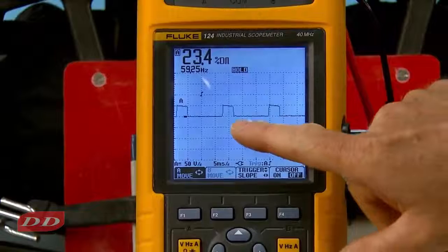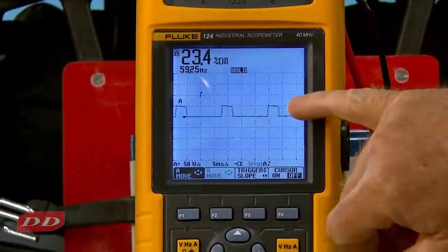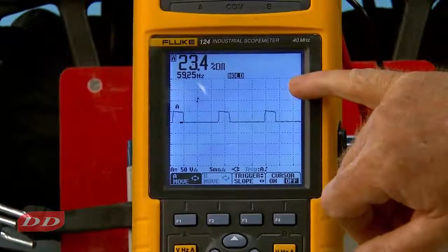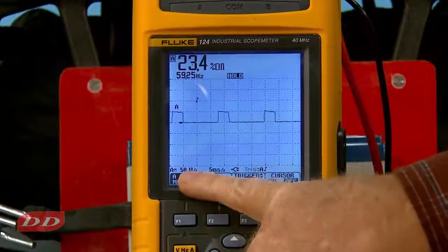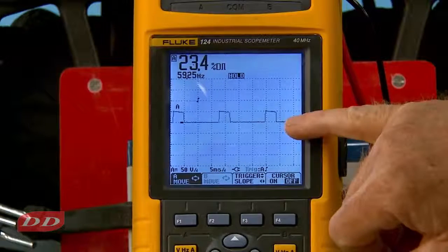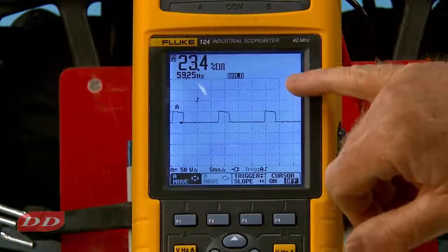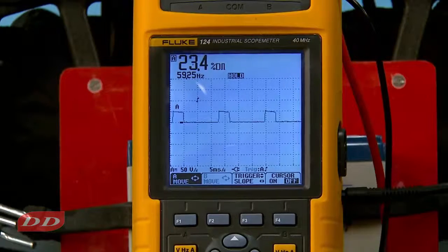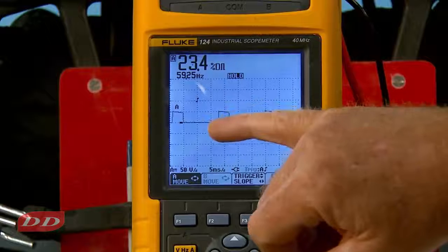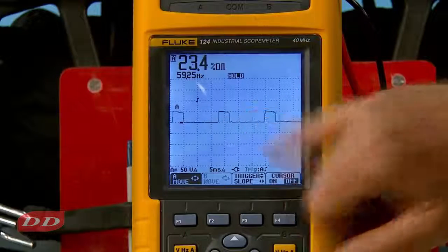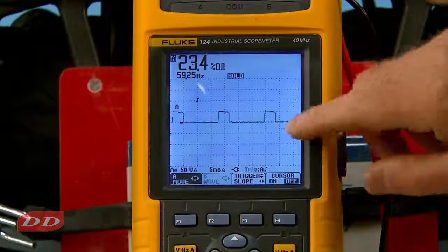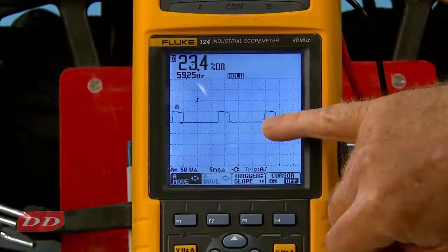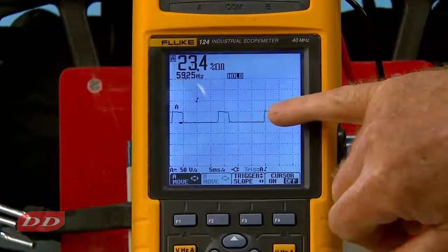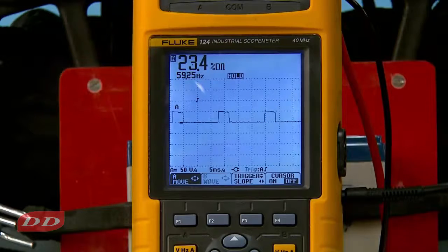Now this is a pulse direct current waveform, as you know. Each one of these divisions vertically is set at 50 volts per division. So this is the zero line, it's 50 volts, 100 volts, 150, 200, like that. The divisions horizontally are 5 milliseconds per division. So what we have here, we can see that the waveform is pretty much at 50 volts, which is what we had dialed in and what the voltmeter said.